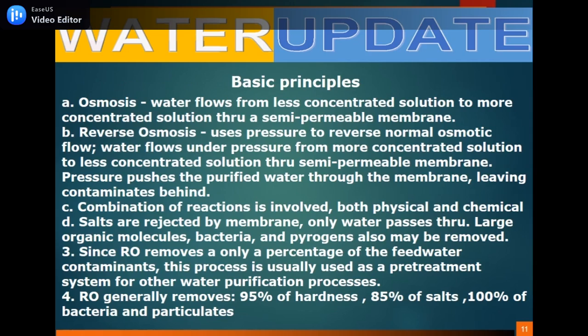The basic principle of osmosis is that water flows from a less concentrated solution to a more concentrated solution through a semi-permeable membrane. In reverse osmosis, pressure is applied to reverse the normal osmotic flow, so water flows under pressure from the more concentrated solution to the less concentrated solution through a semi-permeable membrane. Pressure pushes the purified water through the membrane, leaving contaminants behind. The process involves both physical and chemical reactions. Solutes are rejected by the membrane and only water passes through. Large organic molecules, bacteria, and pyrogens may also be removed. Since RO removes only a percentage of the feed water contaminants, this process is usually used as a pre-treatment system for other water purification processes.